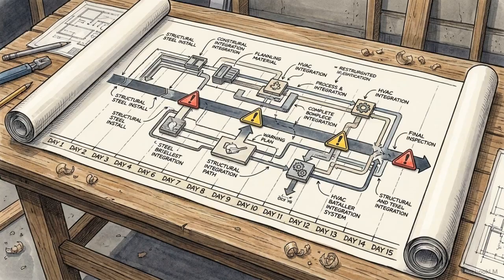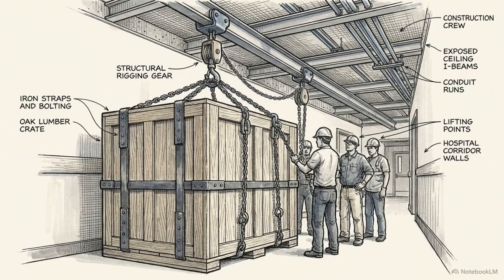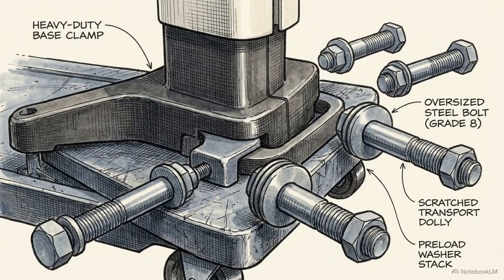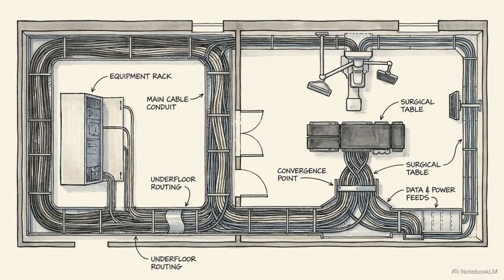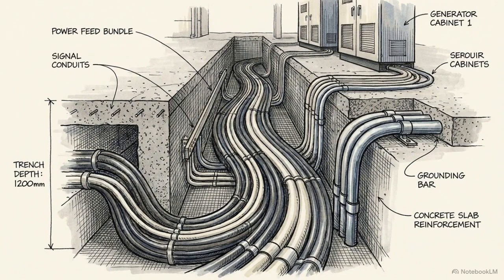With the room prepared, the mechanical installation of the imaging system operates on a tight, highly choreographed timeline, typically executed in 6 to 15 days. On day 0, specialized rigging teams extract the equipment from staging. Heavy components arrive bolted to custom shipping dollies to prevent microscopic internal shifts during transit. By day 2, technicians map the extensive cabling architecture.